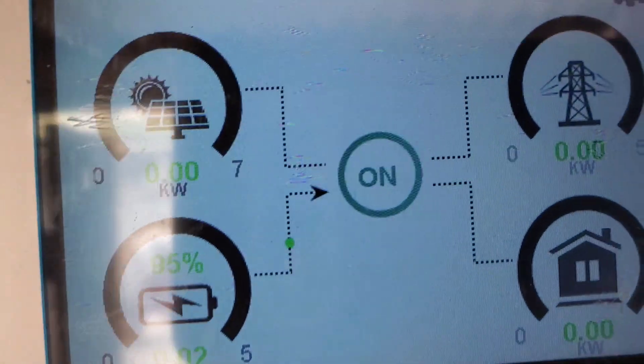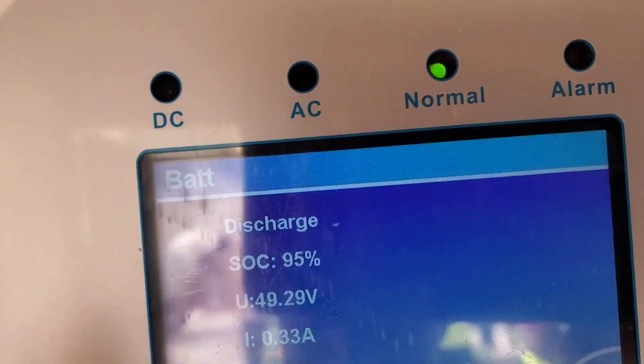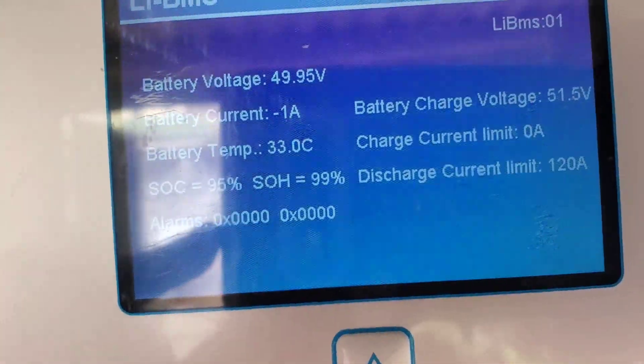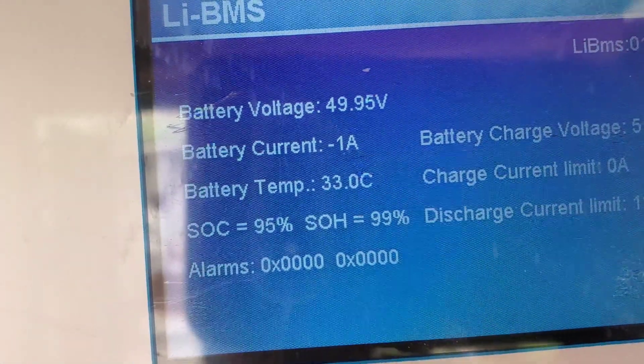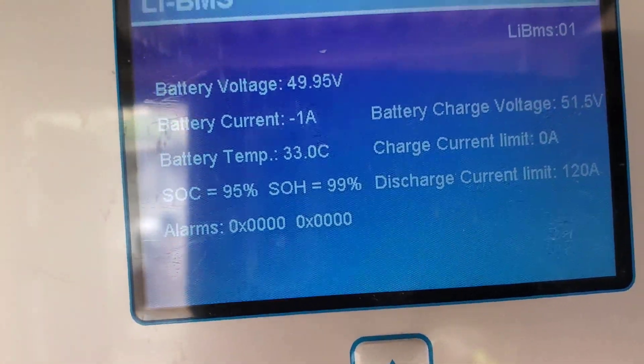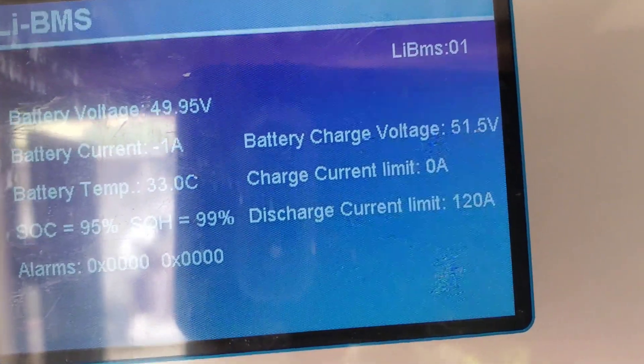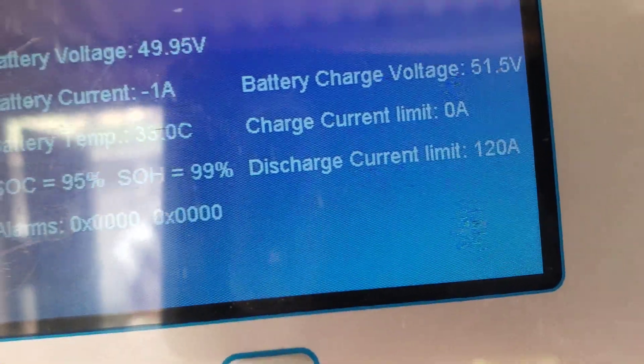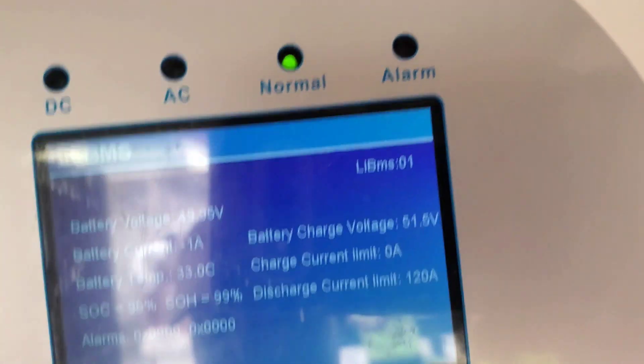As you can see, the inverter is on. Let me check the BMS connection — yes, we have BMS connection. It's showing battery temperature, battery current, state of health, and state of charge. And then battery charge voltage and charge current limit. This charge current limit is 0A, so we cannot charge this battery any further as it is.